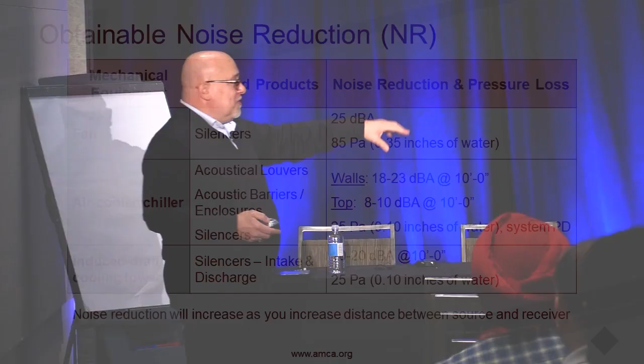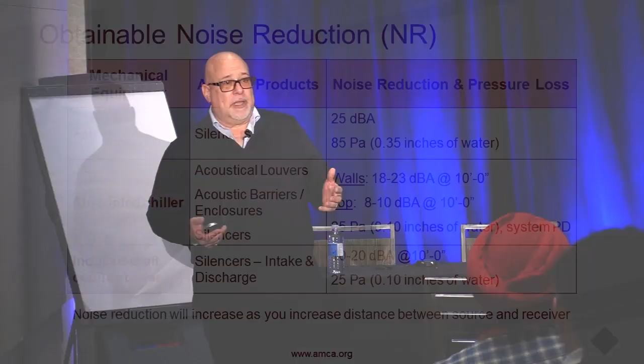So if you're looking at a fan outdoors, either up on a roof or a dust collector next to a building, what's realistic? Well, you can expect about a 25 dBA drop at about 5 feet away from, say, the discharge of that fan, at about 0.35 inches water gauge static pressure drop. That's realistic. If you need more than that, can it be done? Oh, yeah. But you might have to slow that velocity down and slow the airflow down. So it can be done, it might be more expensive.